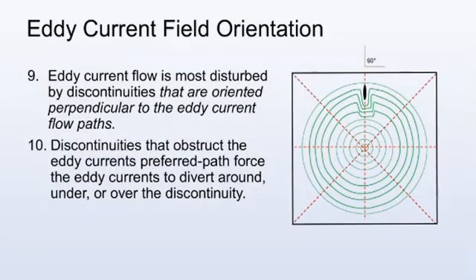Eddy current flow is most disturbed by discontinuities that are oriented perpendicular to the eddy current flow paths. Discontinuities that obstruct the eddy current's preferred path force the eddy currents to divert around, under, or over the discontinuity.